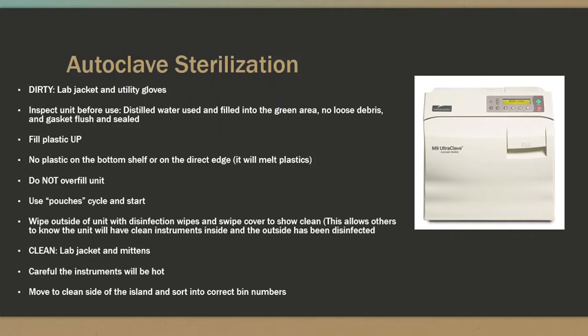Make sure it looks nice and that the gasket is flush and sealed. Make sure that when you're filling the autoclave that you're putting the plastic up and that you're not putting any kind of plastic on the bottom shelf or directly on the edge, as it can melt the plastics. Also, do not overfill the unit. Make sure that the bags aren't stacked on top of each other. The point is to sterilize them, and if it's overly filled, it could block some of the space and prevent the sterilization process. Since we are putting our instruments in pouches, you will see that I am going to be using the pouches cycle, and I'll push start to start it. Let me show you that now.